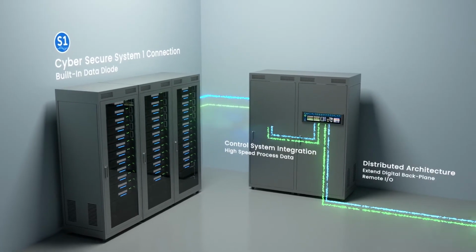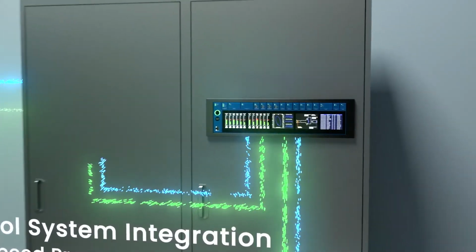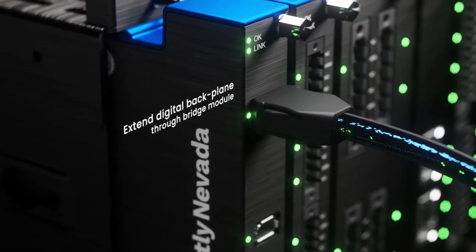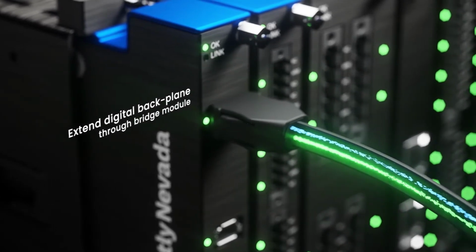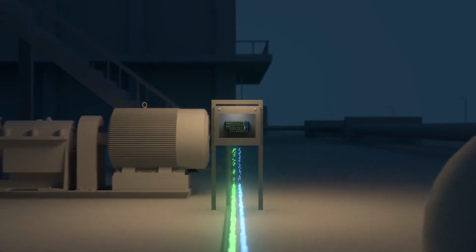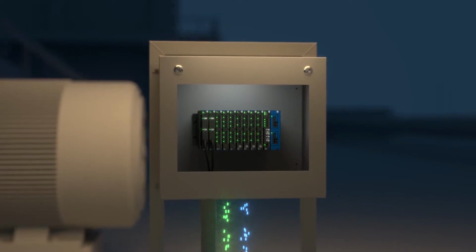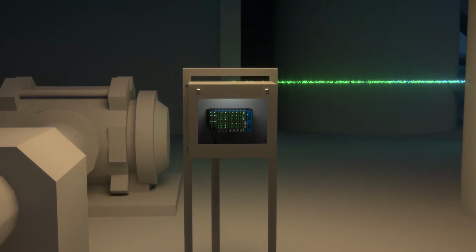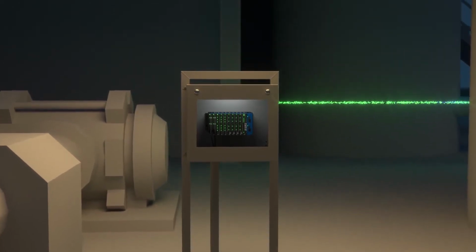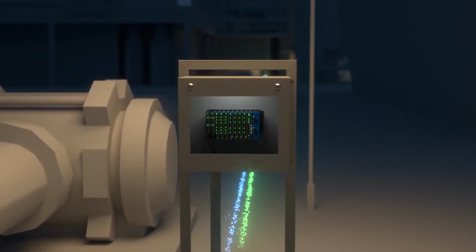Yeah, sure. In the first release of Orbit 60 in the fall of 2021, we're really aligning to the core functionality: radial vibration, thrust, keyphasor, temperature inputs, discrete inputs, relay outputs, protection, condition monitoring functionality, really the core of the platform. As we get into the spring of 2022, we're going to be introducing the more TSI measurements that you would experience for steam turbine applications. That's differential expansion, case expansion, eccentricity, and the list goes on around specific measurements for those steam turbine applications. That'll be complementary in the release next spring.